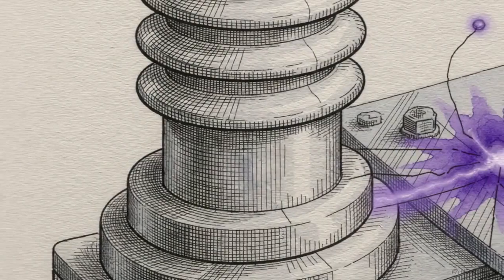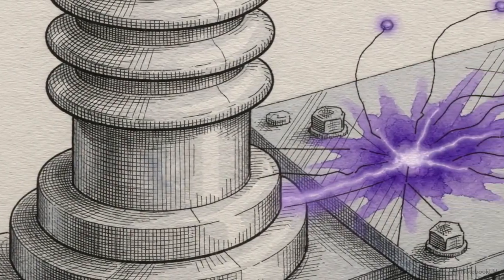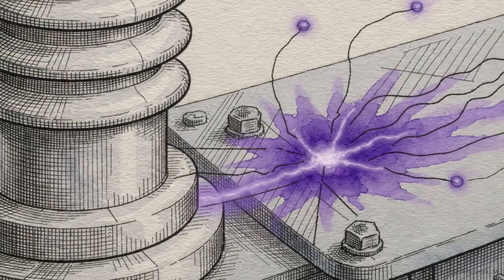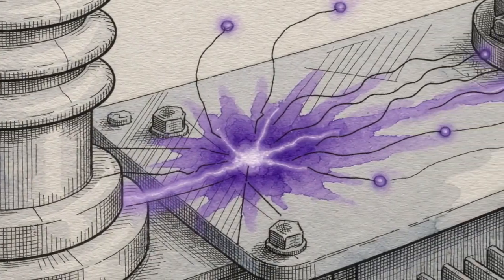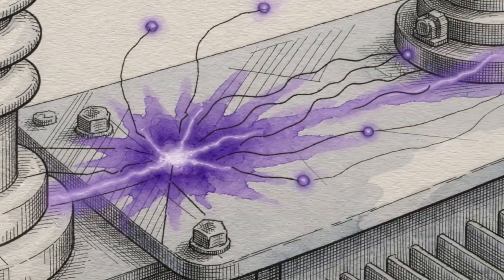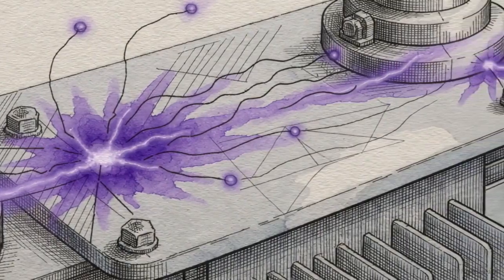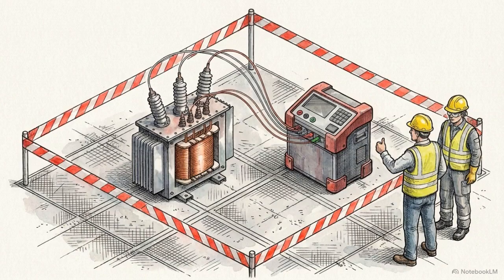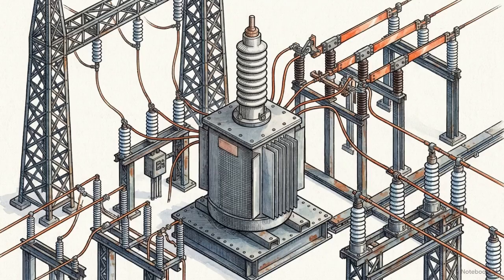During the hold span, operators continuously monitor the environment for signs of physical flashovers, complete dielectric breakdown, or abnormal leakage currents crossing the barrier. Because of the massive energy involved, a strict safety protocol demands that a client or commissioning authority witness physically approves the setup before the high-voltage output is ever armed. Passing this final dielectric test without insulation failure physically proves the unit is structurally ready to handle grid-level operational voltages.